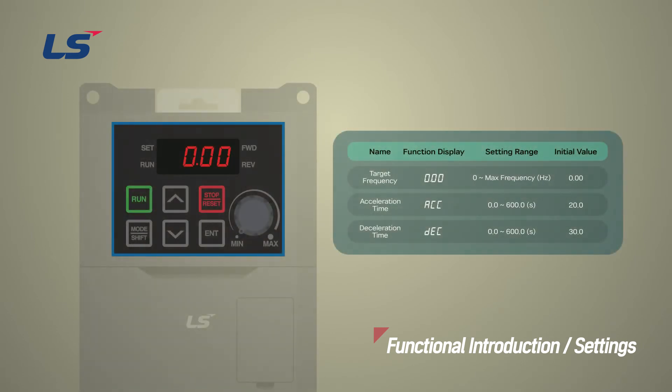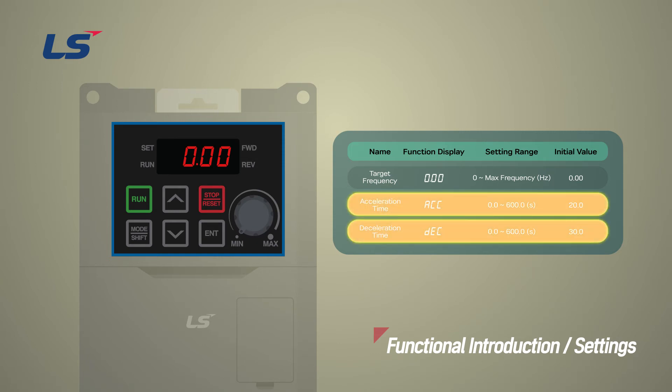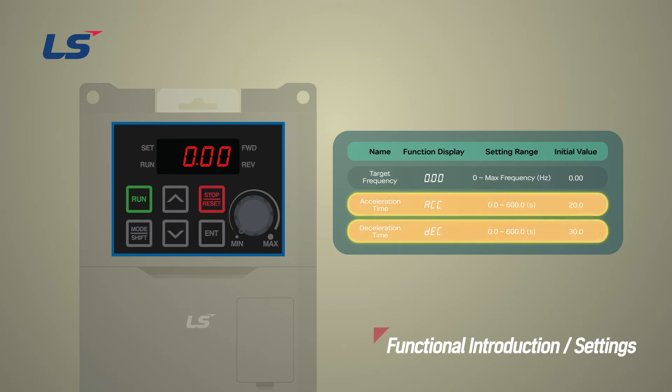The acceleration and deceleration time is defined as the time to reach the maximum frequency, and the time it takes from max frequency back to zero, set by the inverter, and can be set in ACC and DEC of the operation group.